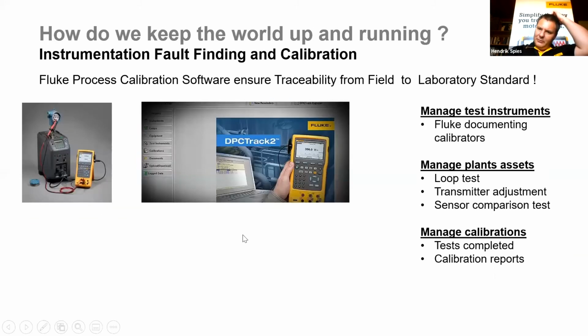Okay, so with this, there's also software. The process calibration software ensures traceability from your field instruments to your laboratory standard, meaning the handheld multifunction documenting calibrators get calibrated by Fluke Calibration higher level accuracy devices, and they are also then calibrated by a standard. So there's full traceability.